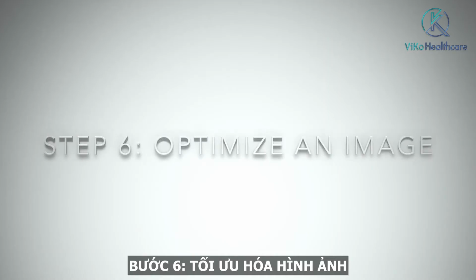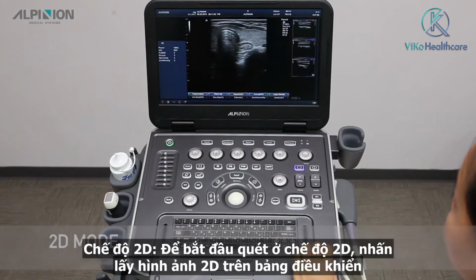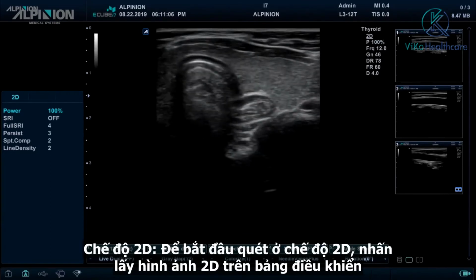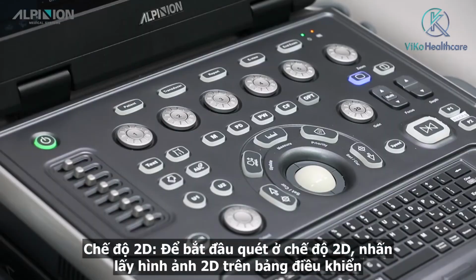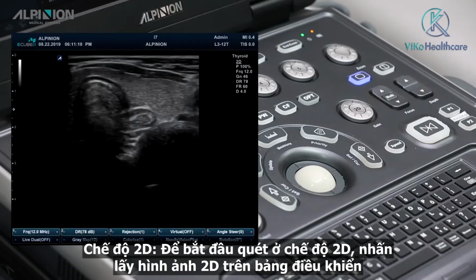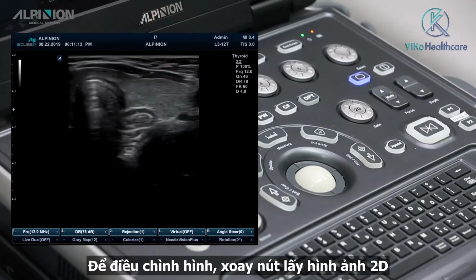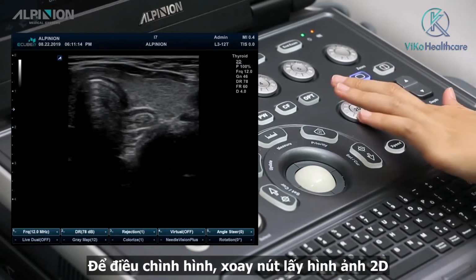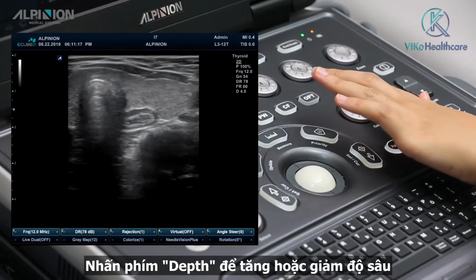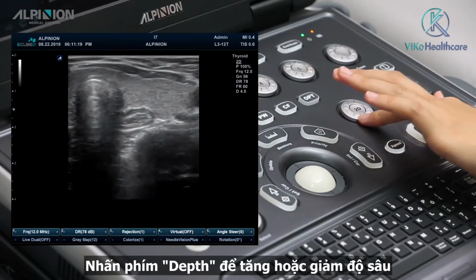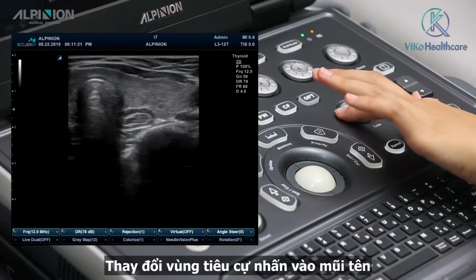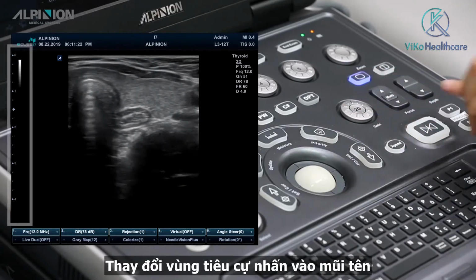Step 6. Optimize an image. 2D mode. To start a scan in 2D mode, press the Gain 2D key on the control panel. To adjust gain, rotate the Gain 2D key. Press the Depth key to increase or decrease depth. To change the focal zone, press an arrow.